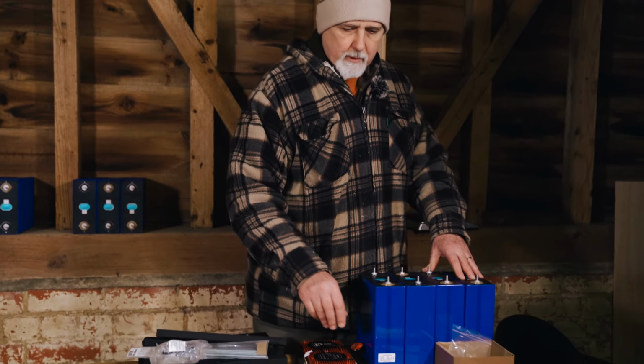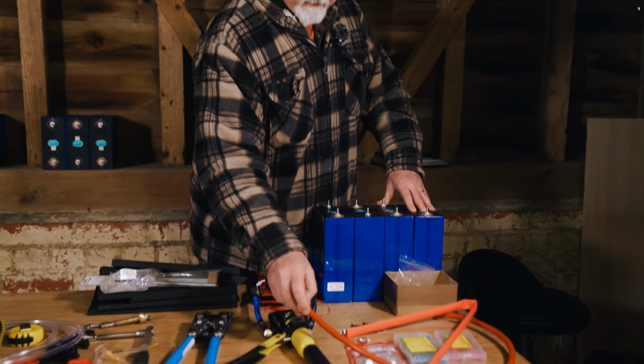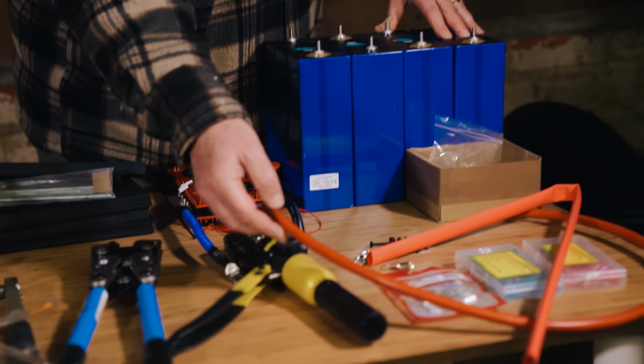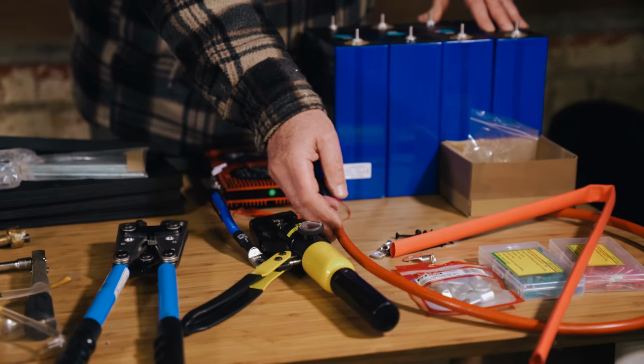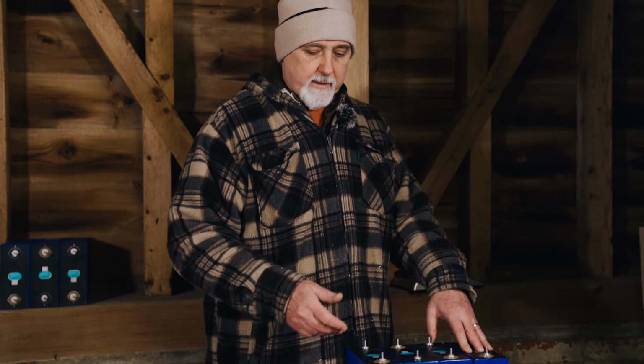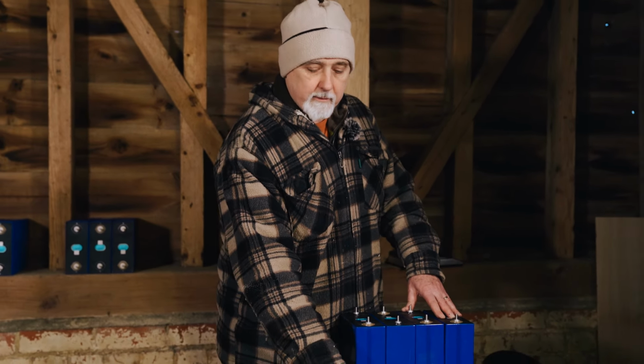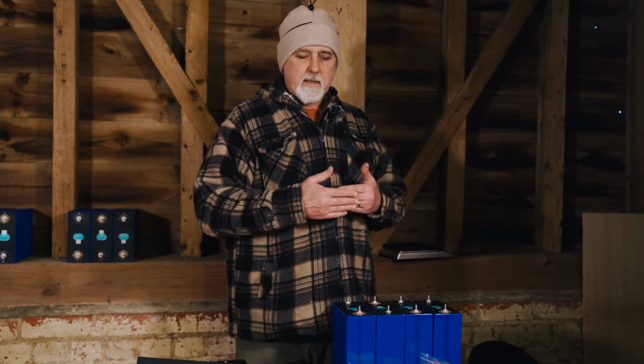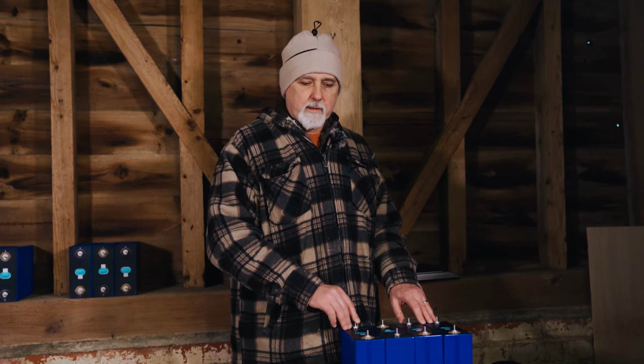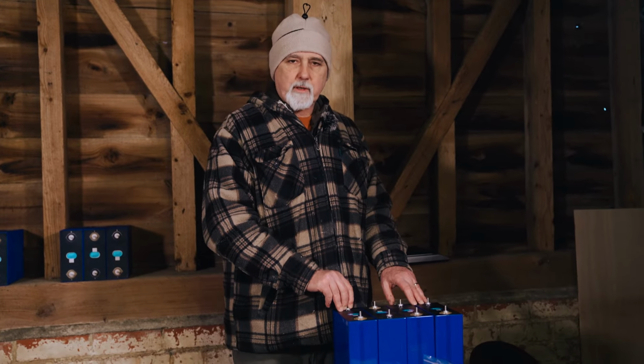You then also would need some red cable, which we are assuming you're going to run straight to a bus bar or a fuse or directly to your inverter or whatever you're doing. So you would need to just work out the length. You don't want too many connections along the way, because each one can build up heat. So you want to go with a fairly thick cable.